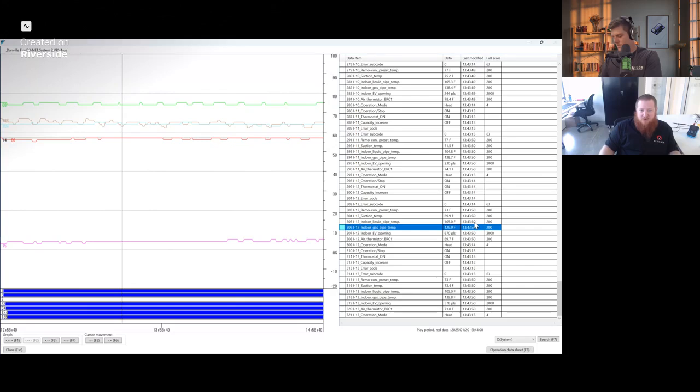But because that pipe is so hot, it's going to potentially cause an irregularity on this gas pipe temperature where the heat may not be there actually, right? The actual refrigerant temperature might not be there, but the temperature of the pipe is hot because it's been radiated heat all the way along that line.